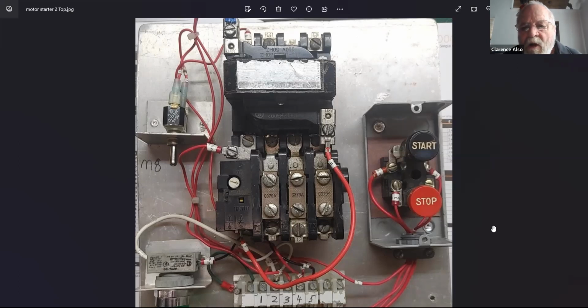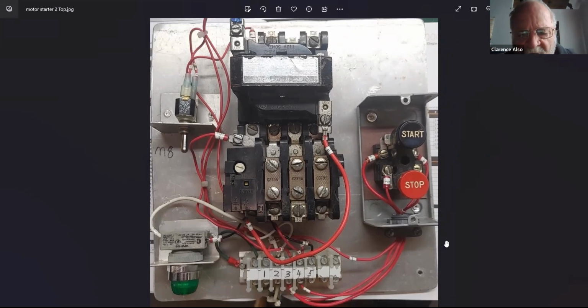3 and 4 are common with each other. They could have had a jumper in between each other. But if you follow 3 and 4 back to terminal 3 and 4 - can you come up a little bit? I'm not quite sure you can see it - that you can see both those wires on 3 go to terminal number 3. So they're actually jumpered together like it is in the drawing.